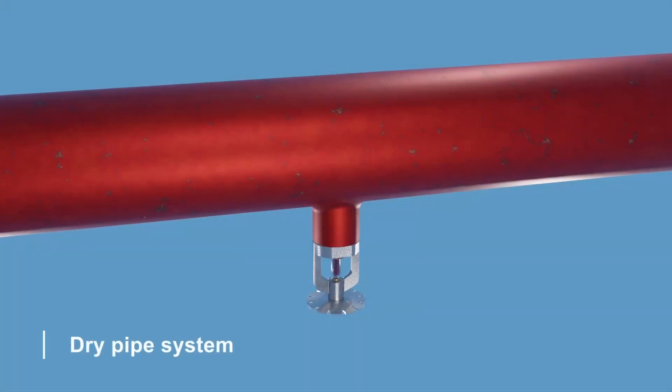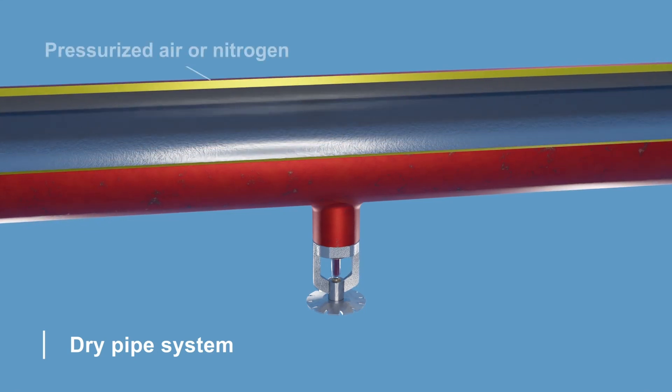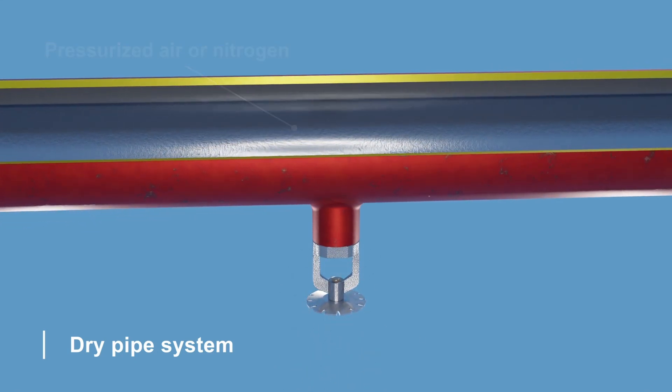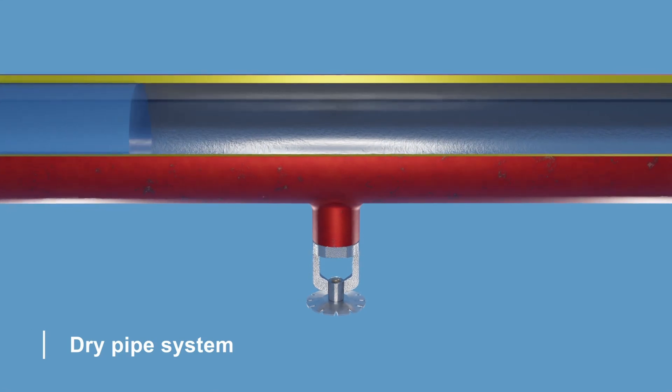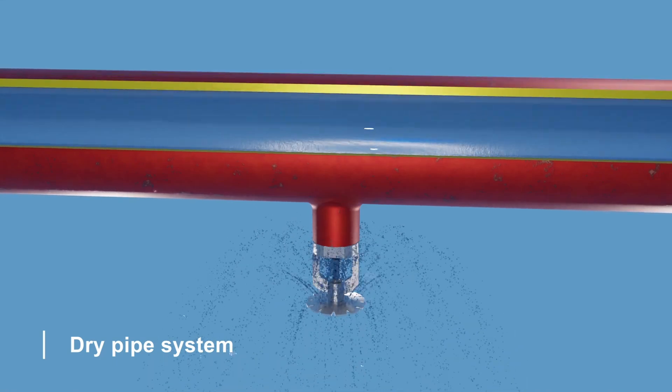Dry pipe sprinkler systems store pressurized air or nitrogen in the pipes instead of water. When the sprinkler head is activated, the air pressure drops, a valve opens and releases water into the pipes. The water then flows through the open sprinkler head onto the fire.